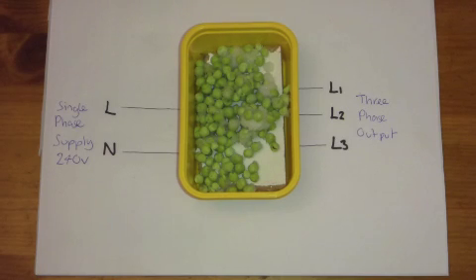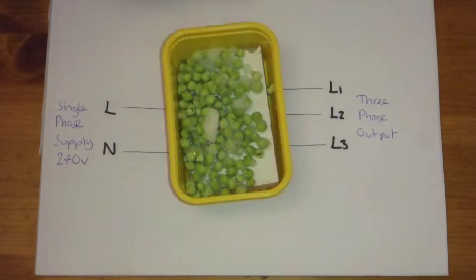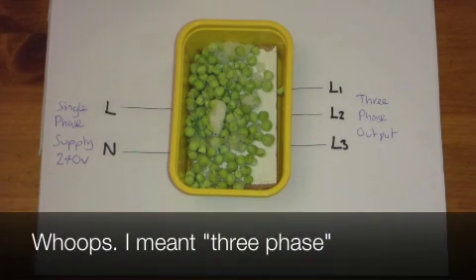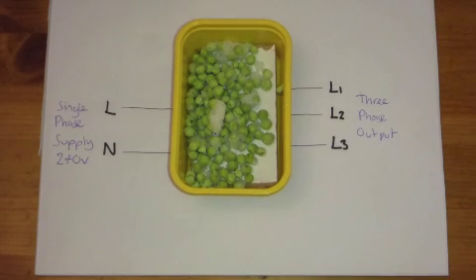What you'll find with these static converters also is they're not really up to running more than one machine and many of them have a minimum motor output as well as a maximum. So they might be sized to run between three and six horsepower. I don't know that many people who buy a three phase piece of machinery and then don't buy another one in a couple of years time.